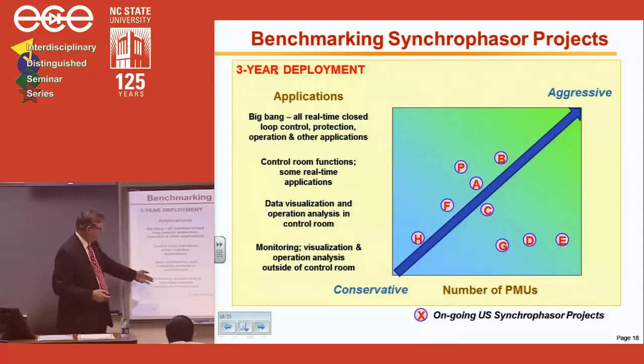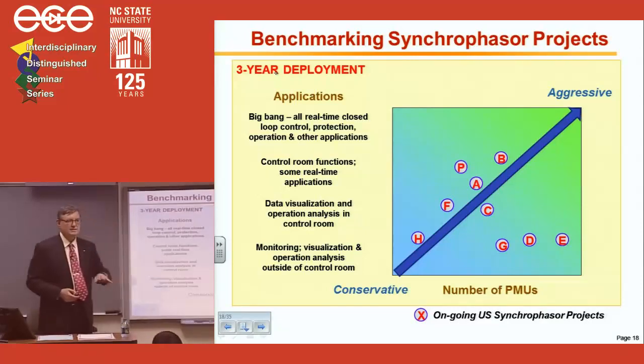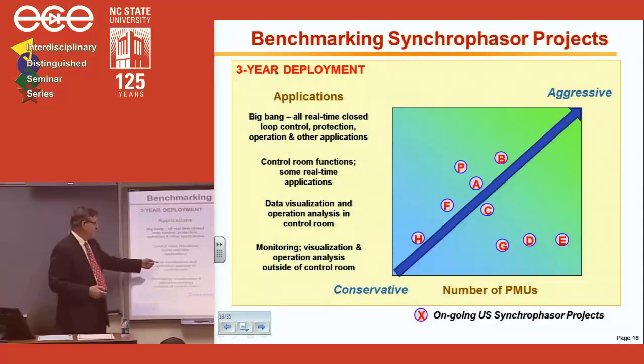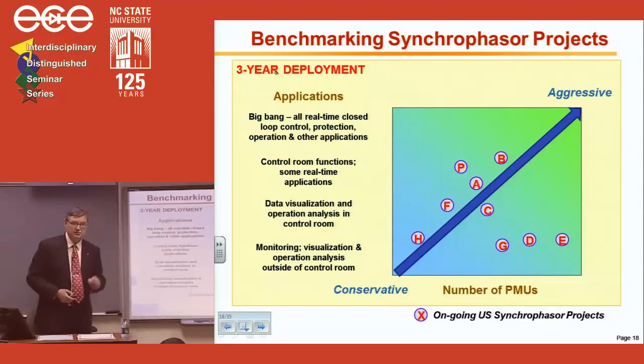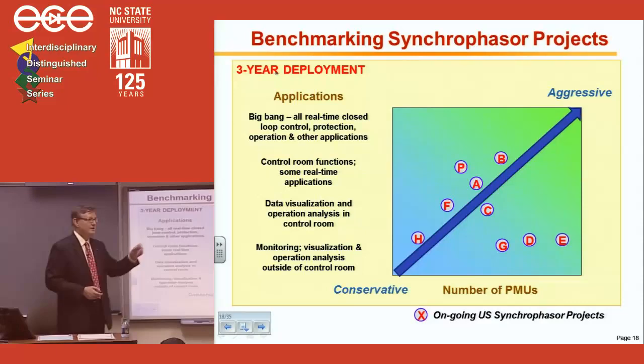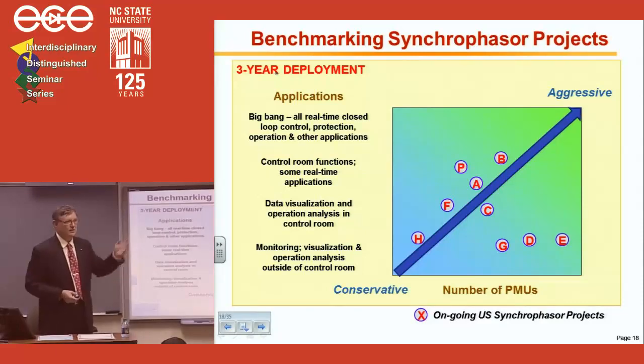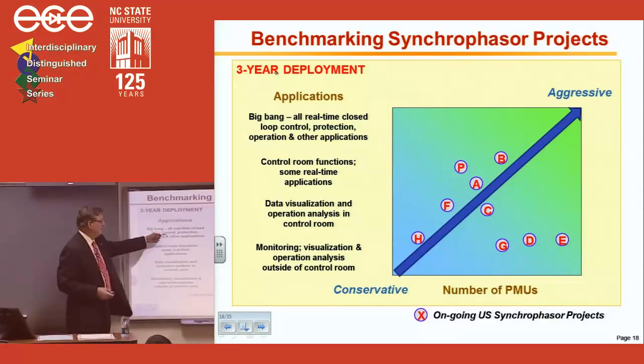Applications can just be monitoring, that's it, you monitor and analyze outside the control room. The next level is you visualize in the control room. The third level is real-time applications, where you do something, you trip the line, you switch a shunt capacitor off or on. The big bang is full-time closed-loop control, protection, operation, and other functions.